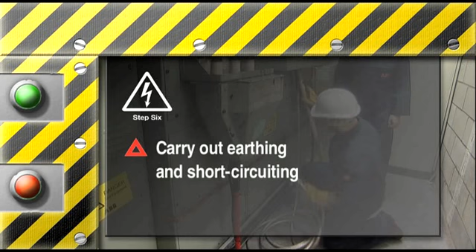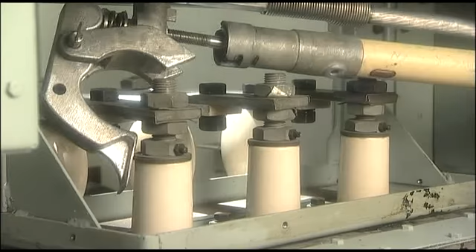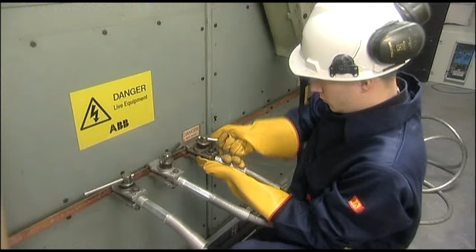Step 6. Carry out earthing and short-circuiting. Earthing has two main functions. Firstly, it ensures the equipment is free of any residual charge or induced voltages during the work. Secondly, it should be capable of short-circuiting any fault current caused by a failure to disconnect in Step 2.